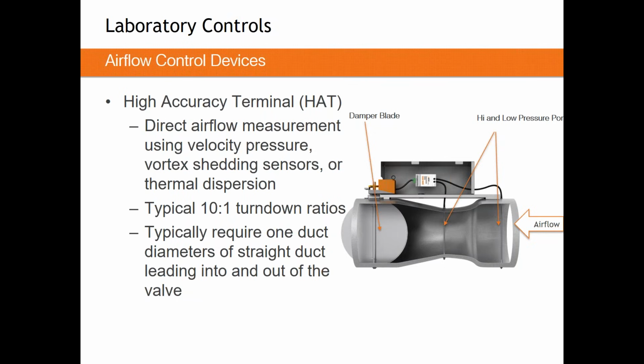when you're measuring pressure. That to a point, really, measuring larger pressures is easier than measuring small pressures. Measuring in the mid span or the top end of the span of a pressure transducer makes the transducer much better at its job. Trying to measure right down to the minimum of what your transducer or sensor can do is extremely tough and not the most accurate thing in the world. So that's why we amplify that pressure drop through a high accuracy terminal. And we do pay a bit of a penalty on the horsepower at your fan, but we get much higher accuracy. What kind of accuracy?